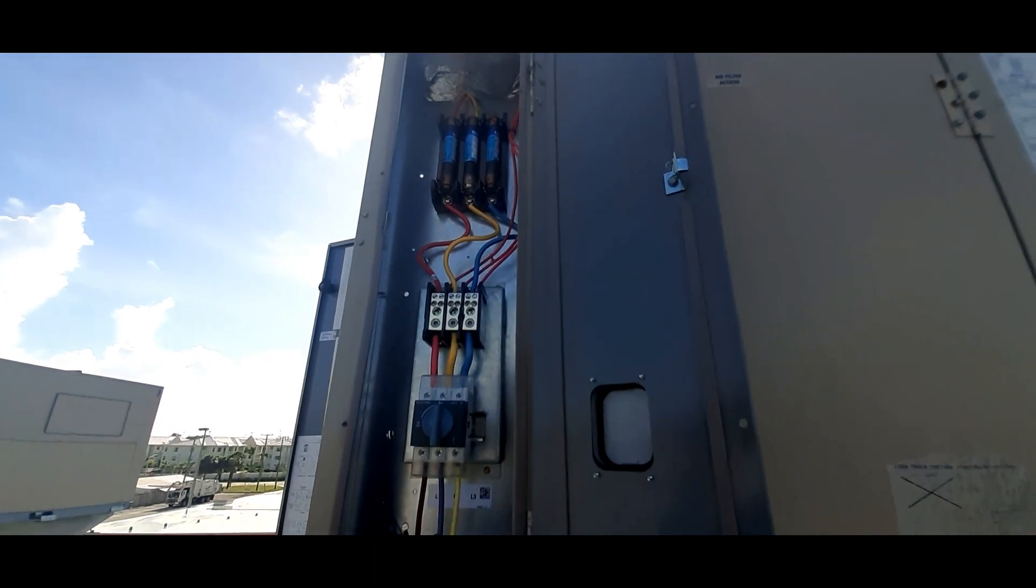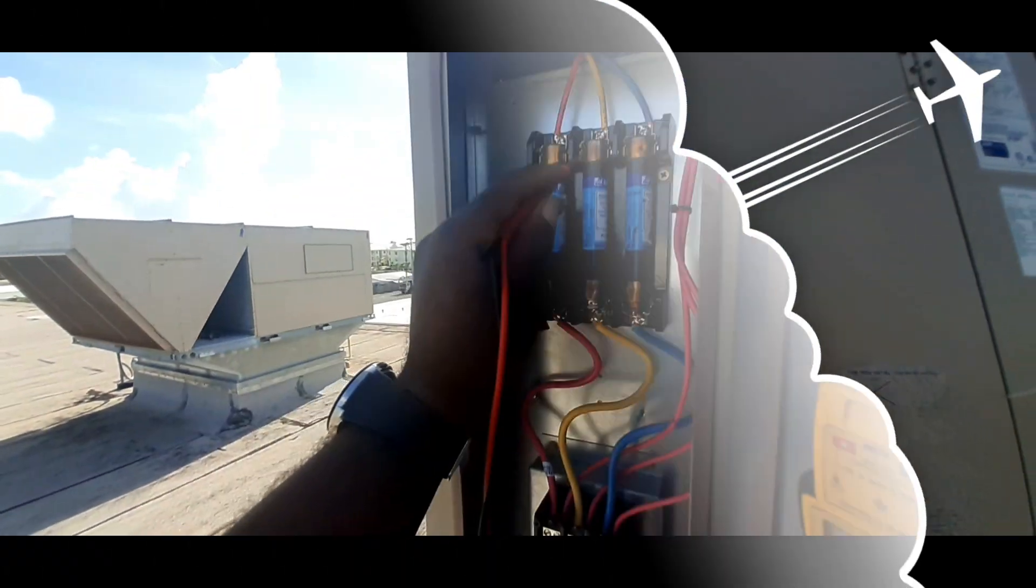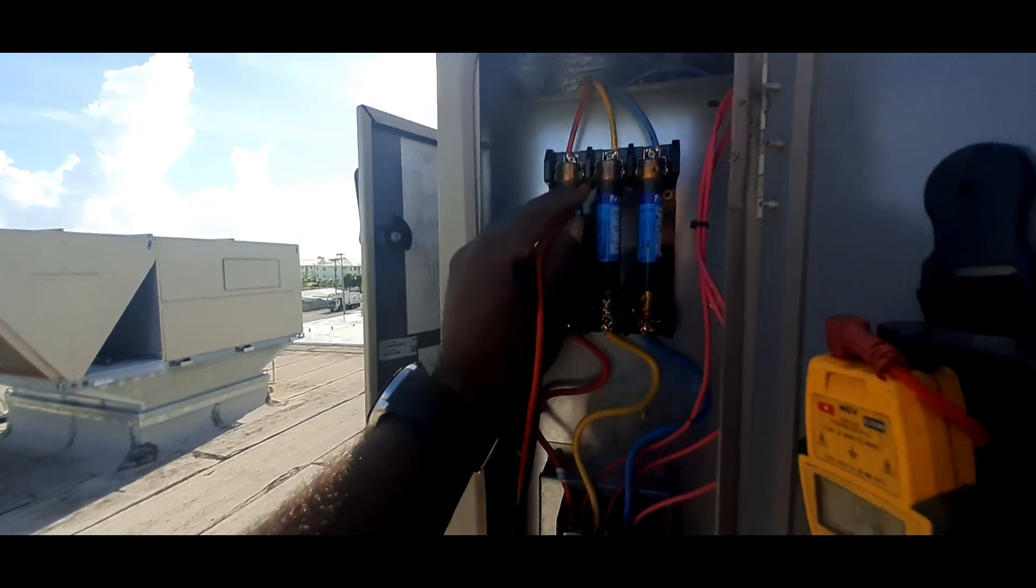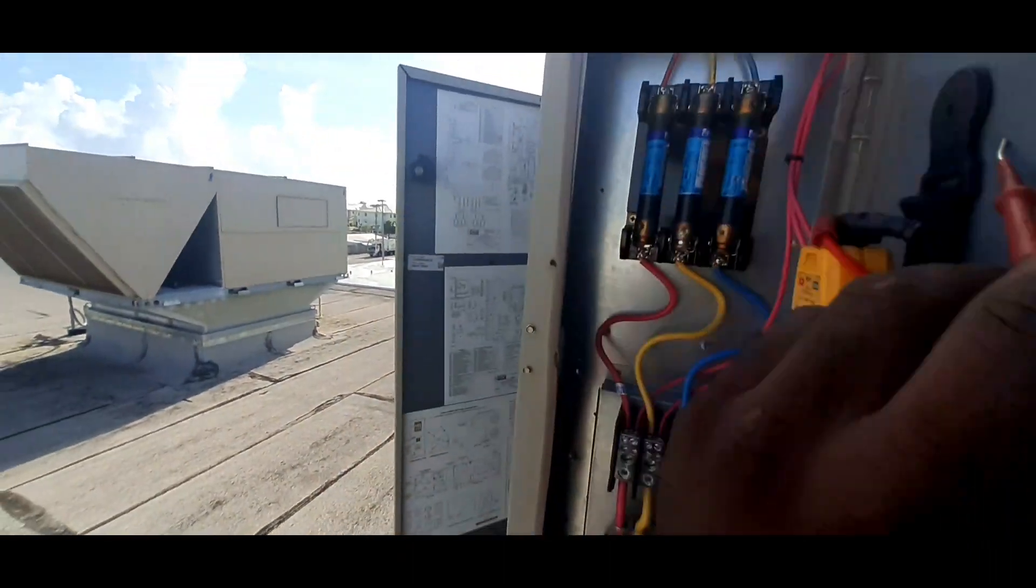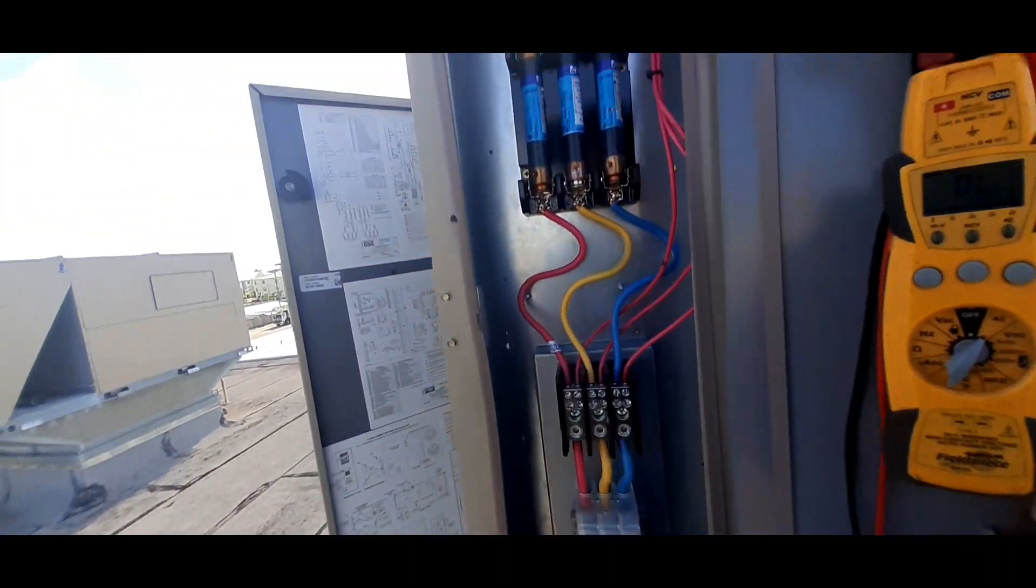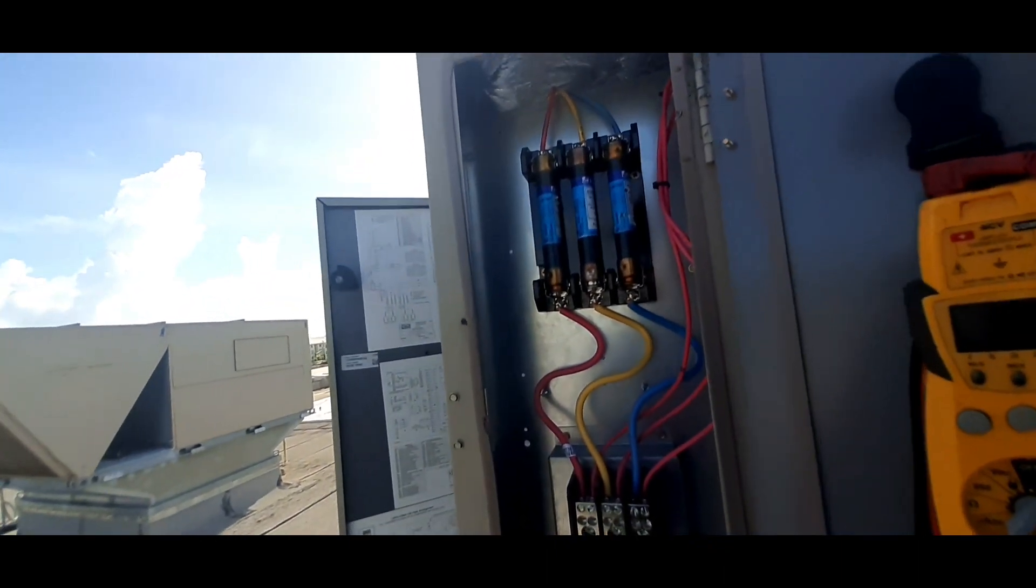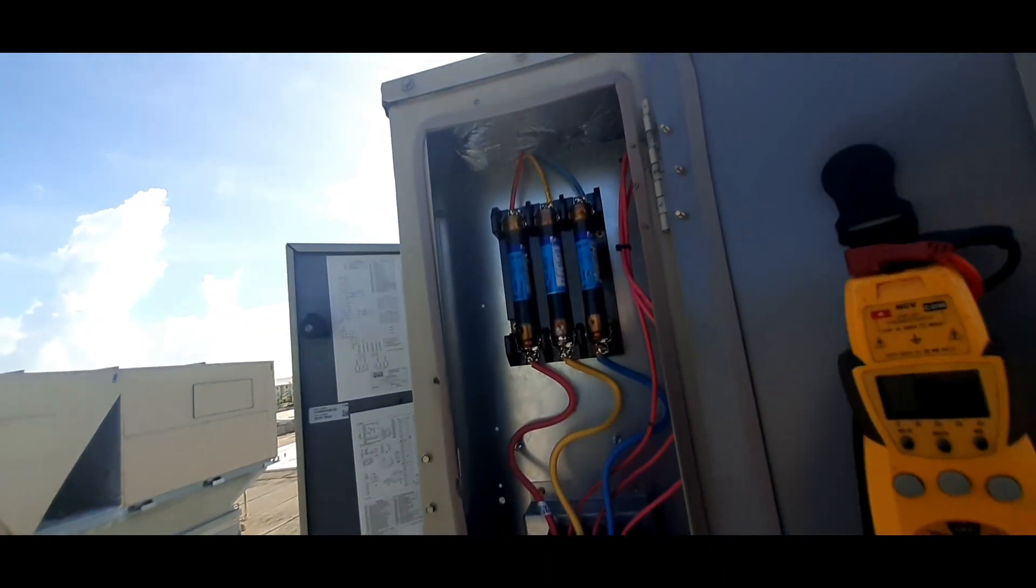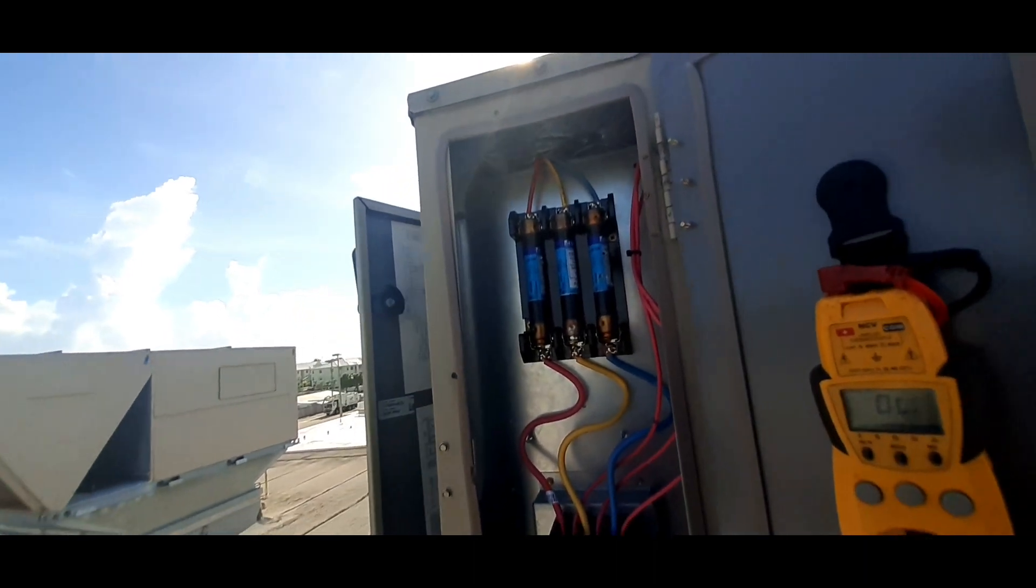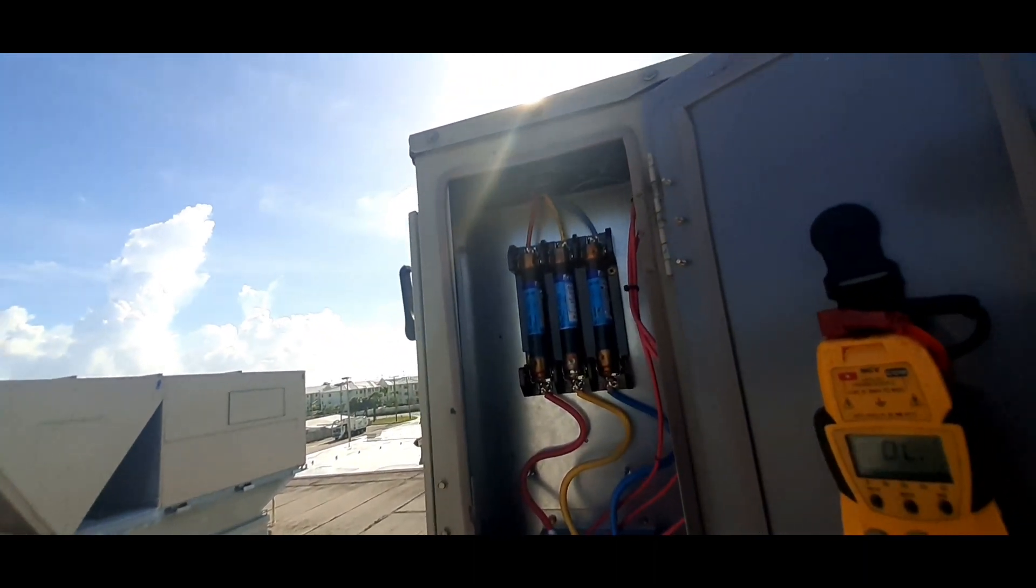All right, so that's my fuses. All right, so I'm just checking out this fuse here. This fuse here is open. I have my meter on continuity, so we got a blown fuse. That's why we don't have the proper 24 volts. Something shorted out this fuse. Let's just check through the circuits and see what we find.